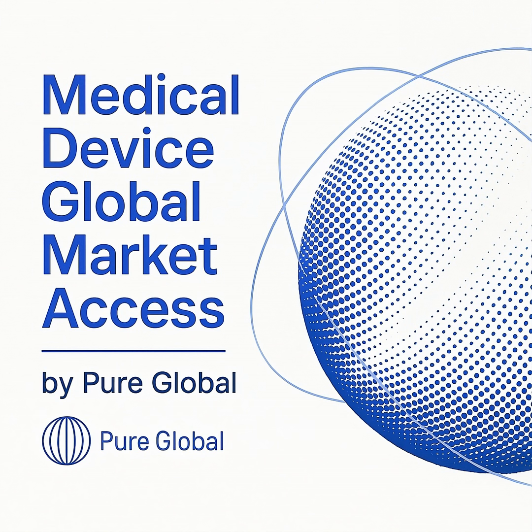It requires detailed procedures for production and service activities, including the validation of critical processes like sterilization. Finally, it establishes a framework for measurement, analysis, and improvement, which covers vital post-market activities like complaint handling, reporting to regulatory authorities, and implementing effective corrective and preventive actions, known as CAPAs.